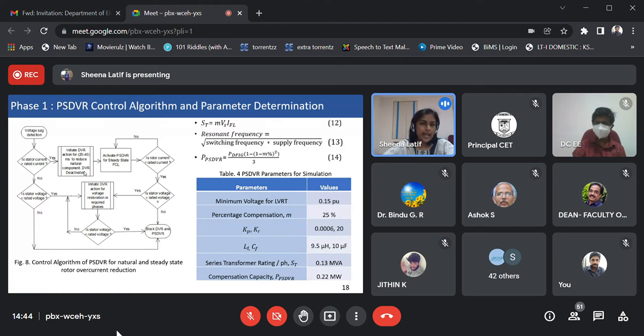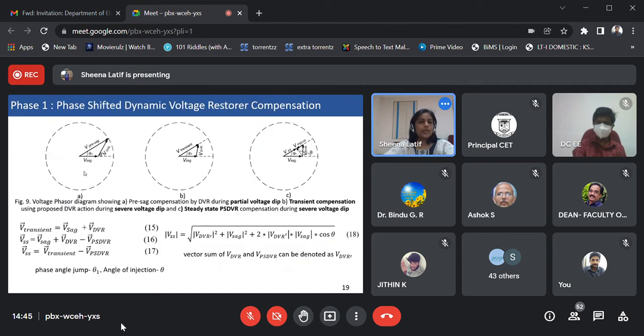As soon as a voltage sag is detected, the stator current is checked for any overcurrent. If any overcurrent is detected, the PS-DVR activates the DVR mode of voltage restoration for the initial 20 to 40 milliseconds, after which a steady state period begins and the PS-DVR mode is activated for steady state fault current limiting. This continues until the rotor current is regulated to the rated value. Even after the rotor current regulation, any voltage dip occurring in the stator can be controlled using a DVR action. The parameters determined for the PS-DVR are given in table 4. So, for phase shifted DVR compensation, the modes of PS-DVR are explained using the voltage phasor diagram.